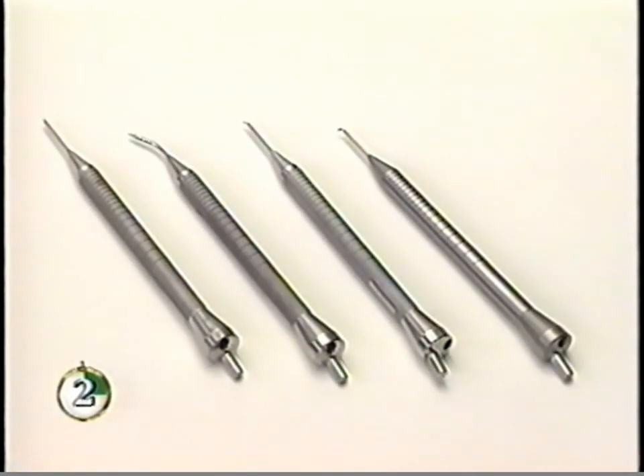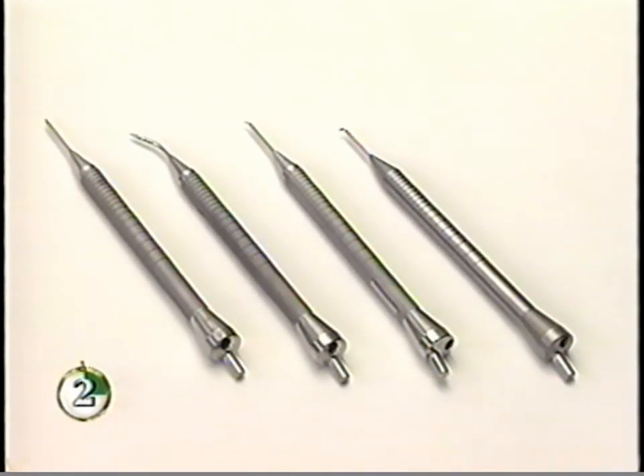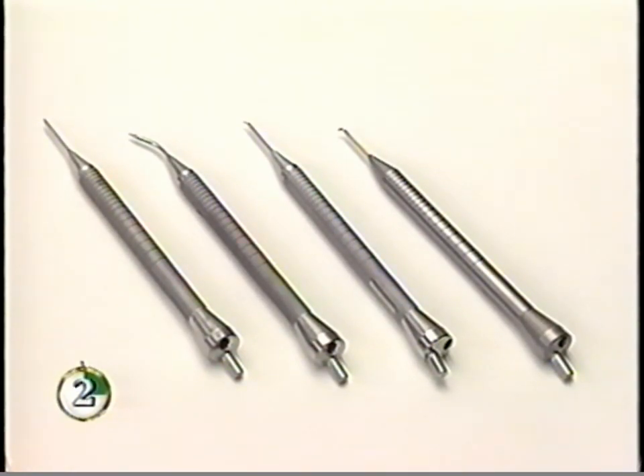Series 8000 handpieces, used in the IA mode, remove cortical material by aspiration while maintaining chamber pressure by irrigation. Series 8000 tip ports all measure 0.3 mm and come in straight, curved, 45 degree, and 90 degree configurations. These 4 tips have built-in metal irrigation sleeves and require no tip cap sleeve.